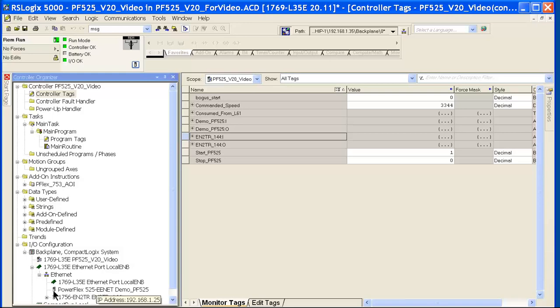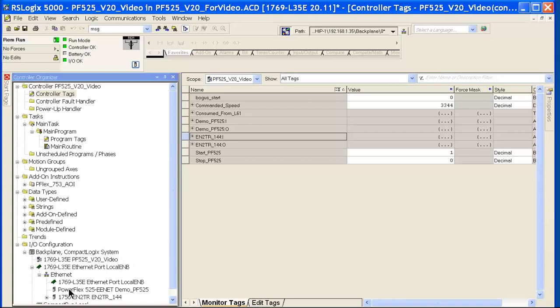It doesn't have a yellow triangle here. Sometimes what might happen if you don't download the file offline to the drive, the parameters won't match what this RSLogix 5000 ACD file has and you would end up with a yellow triangle here. If that happens, you just need to go offline and download to the drive first.